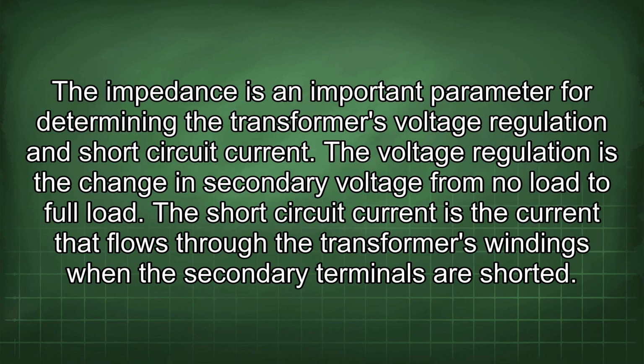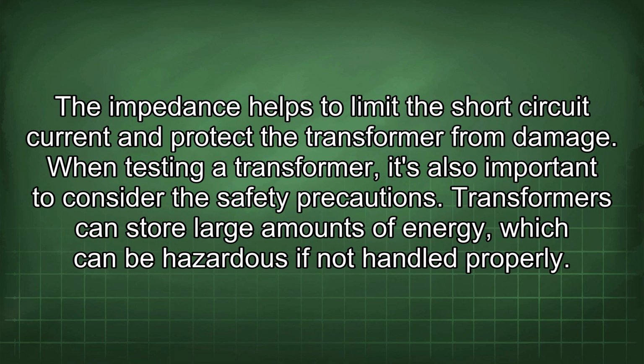The impedance is an important parameter for determining the transformer's voltage regulation and short-circuit current. The voltage regulation is the change in secondary voltage from no load to full load. The short-circuit current is the current that flows through the transformer's windings when the secondary terminals are shorted. The impedance helps to limit the short-circuit current and protect the transformer from damage.